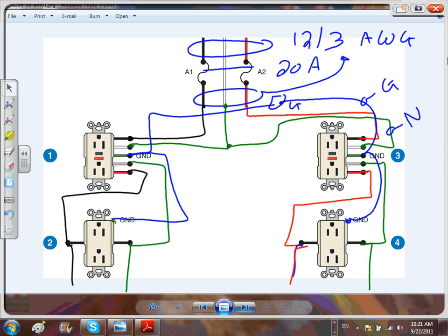But if you read right through it, they don't, because they don't exist. If you go to the upper right corner, it says this requirement becomes effective January 1st, 2014, a year from now. So if you want to change a receptacle in your bedroom right now, no problem. But if you change it effective January 1st, 2014, you have to change it.